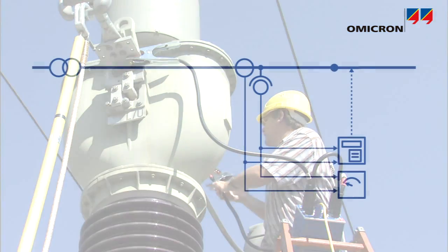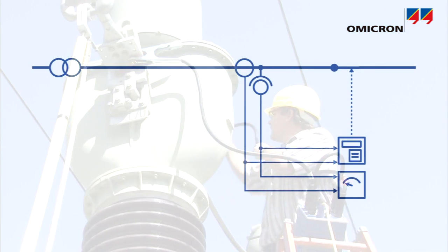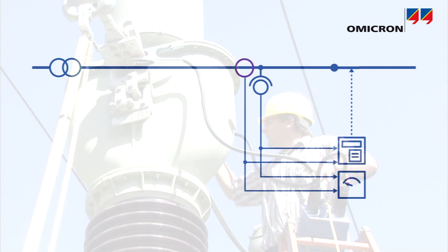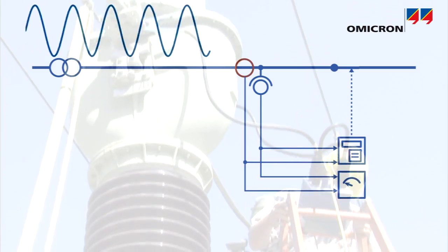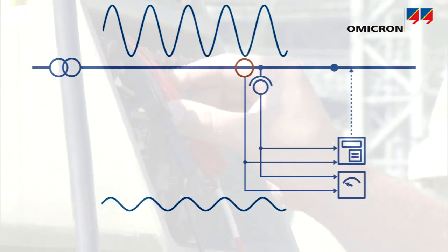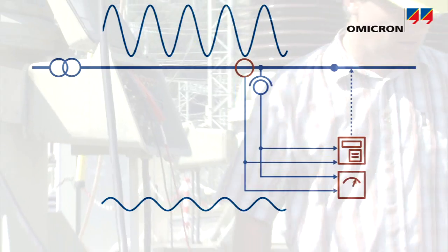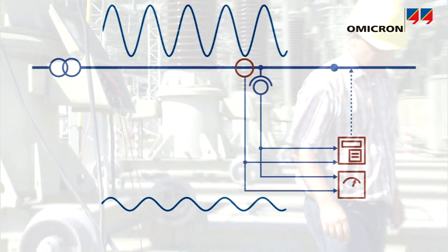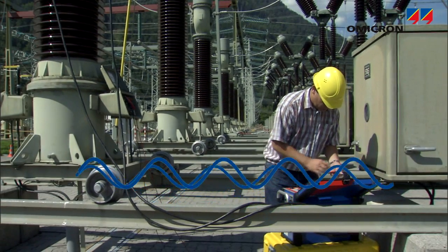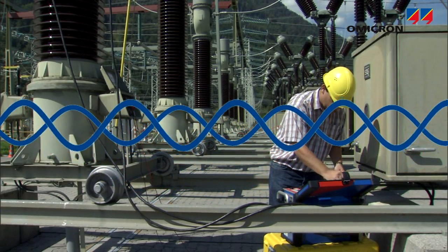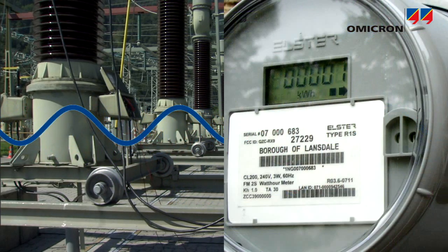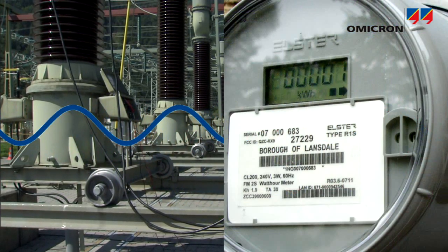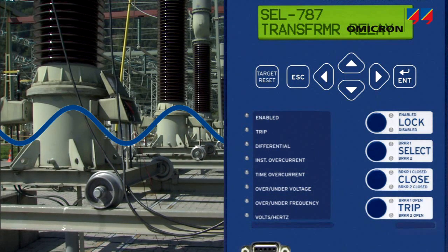The testing of individual components is based on their respective functions. Current transformers, or CTs, have to transform the primary current to a secondary current needed for control, protection, and metering systems. The secondary current must be accurate in amplitude, polarity, and phase in order to allow accurate metering and proper operation of the protection system.